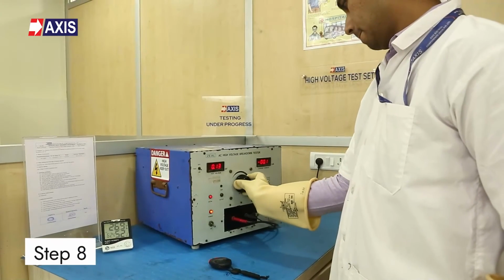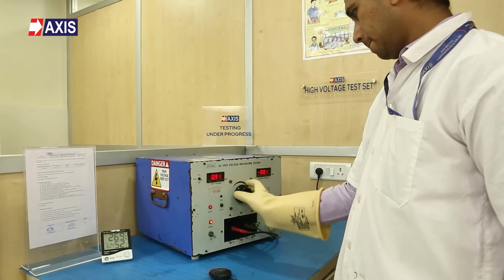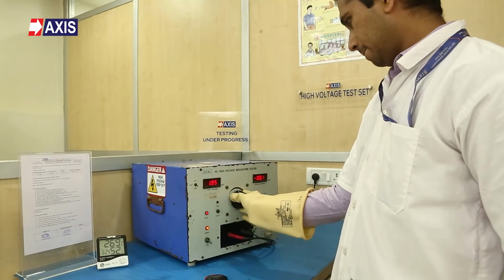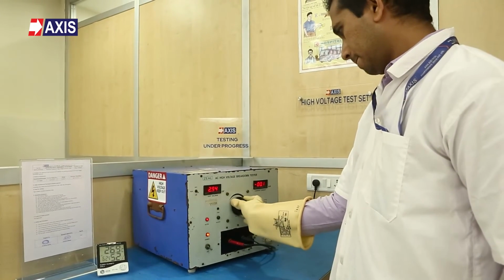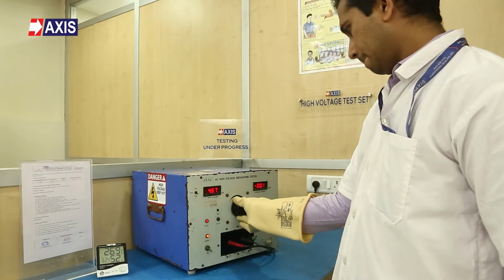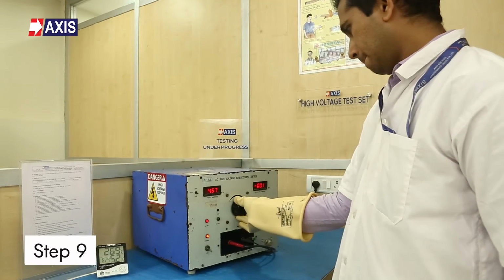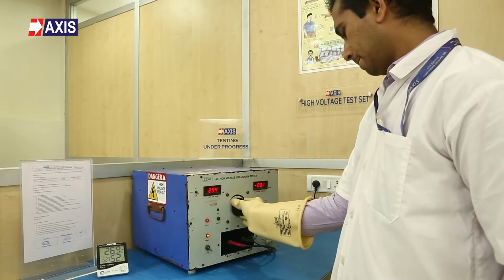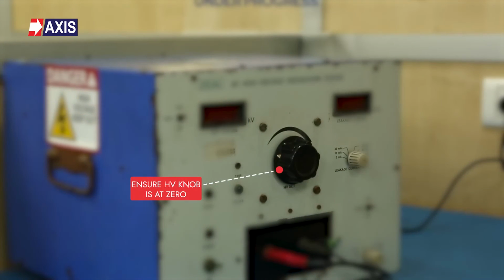Step 8. If the HV tester trips and the buzzing sound stops before the required duration, it means the sample has failed in sustaining the desired high voltage level. Step 9. After the test, rotate the HV knob back to the 0 position.